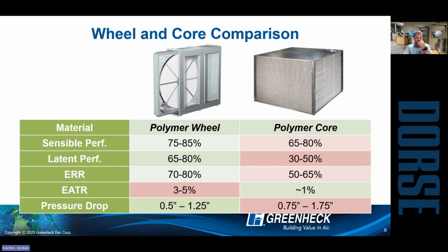The other one that I'll point out there is pressure drop, right? So typically we see less pressure drop on a wheel. It's a thinner media than a core. These are just sort of average ranges that you might expect here. Where that really comes into play, we'll talk about in a minute, is fan power, right? So typically the fan power requirements on a core are significantly higher because we need more energy to push that air across that deeper media, right? So that's going to be a big advantage of a wheel.